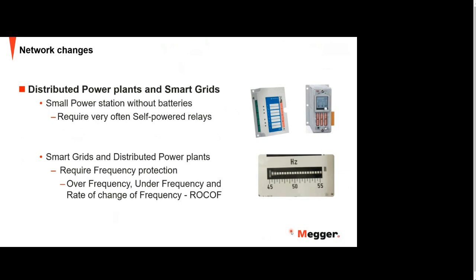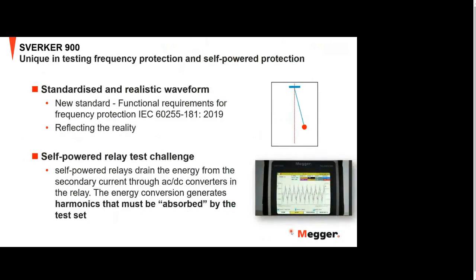Also, in the smart grids and distributed power plants, they will require frequency protection, like over frequency, under frequency, and rate of change of frequency, the ROCOF protections, for example. Because the frequency is very important to have a stable network and a stable supply in the network, not to have big outages in the network. So actually, Sverker 900 is unique in testing frequency protection and self-power protections.